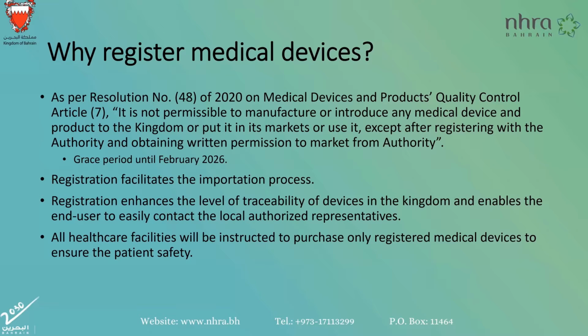Registration enhances the level of traceability of devices in the kingdom and enables the end user to easily contact the local authorized representatives, since all registered medical devices will be published on NHRA website along with their authorized representative. All healthcare facilities will be instructed to purchase only registered medical devices to ensure the patient safety. So as a result of that, registered medical devices will have an advantage over devices that are not yet to be registered.